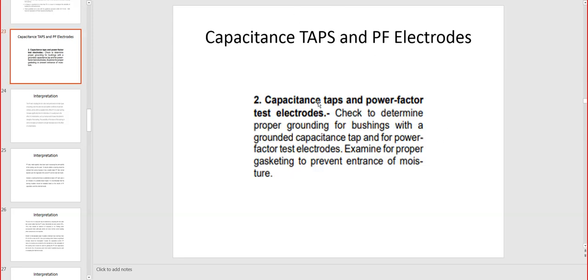Taps and power factor electrodes. So capacitance taps and power factor test electrodes are checked to determine proper grounding. A lot of the time, and it happened to us as well, not connecting the grounding and the instrumentation properly to the tap can lead to a wrong reading, and definitely the conclusion will be, you know, not correct, that the tap is damaged. Eventually it is not. And if you redo the test, we will see it is actually in perfect order, but the test was wrong because of the connection of the instrumentation to the tap and to the ground.